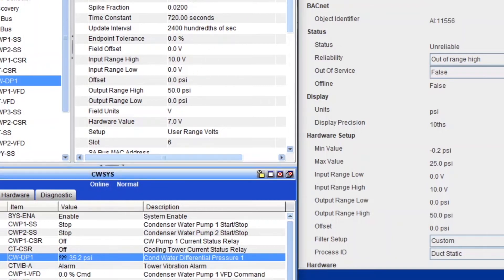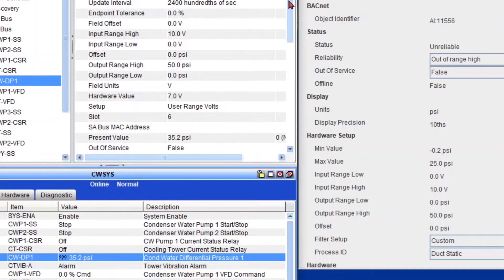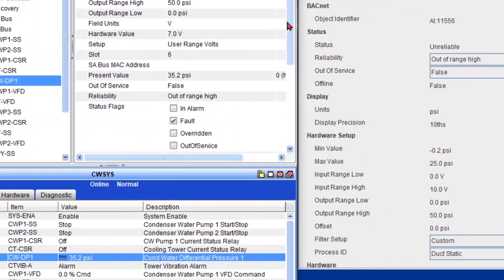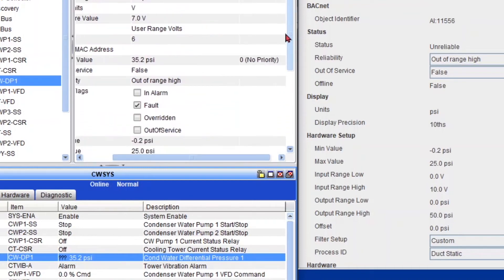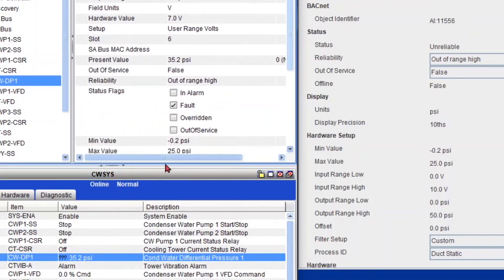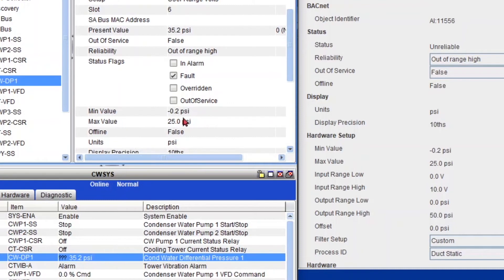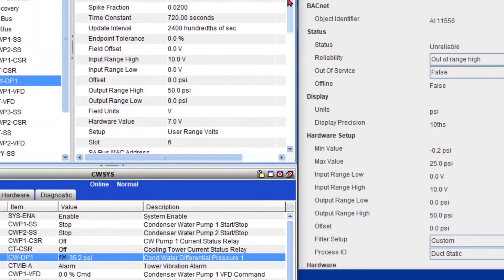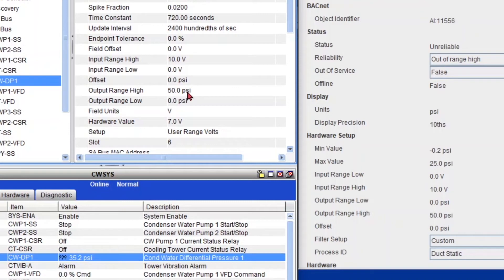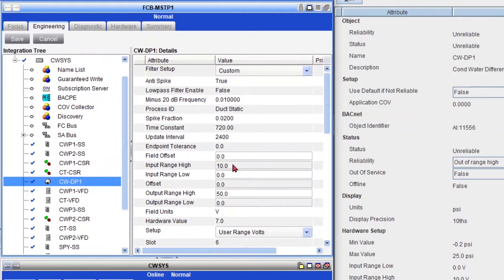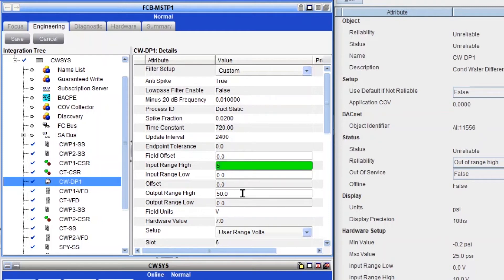And you can find these min and max values in Metasys as well, right here. Right here. So you can also change them from here, but we're not going to do that. We're going to fix it in a different way. Since we mentioned before that this sensor was actually a 0 to 5 volts and 0 to 25 PSI, that's actually going to be within the range here. So let's do that.